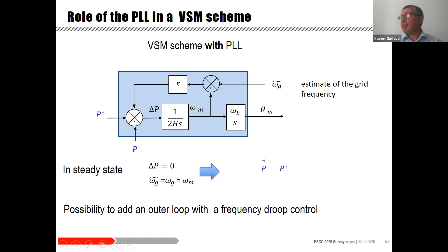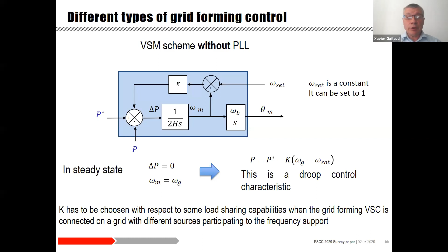If we don't have this PLL, the power difference, delta P, of course, is still equal to 0. Omega M is also equal to omega G. But omega G is not always equal to omega set. It results in a relation between the active power and the grid frequency, which is exactly the same equation as a classical frequency droop control characteristic. This is what we call a kind of compulsory frequency support, which is not always wanted for any kind of sources. K has to be chosen with respect to some load sharing capability when the grid forming VSC is connected on a grid with different sources participating in the frequency support.